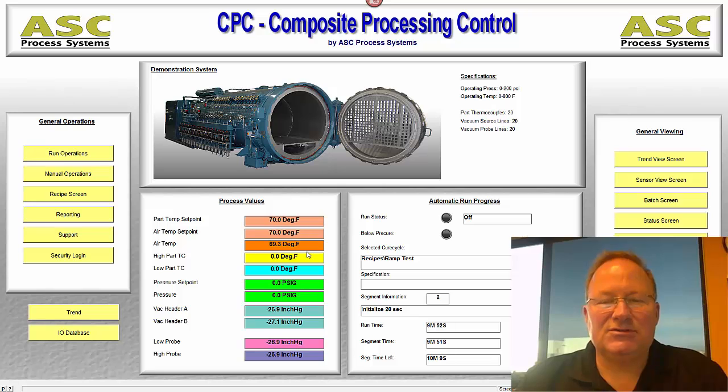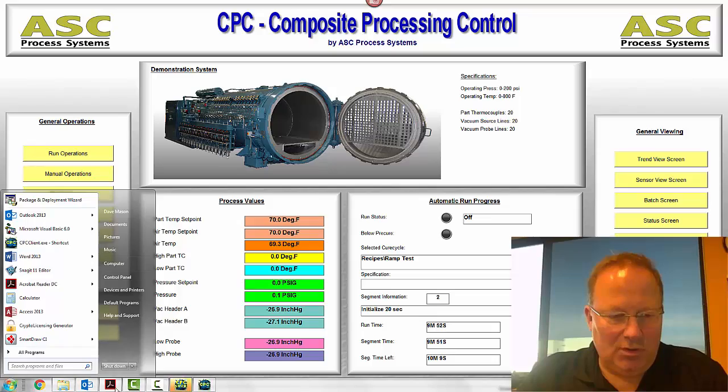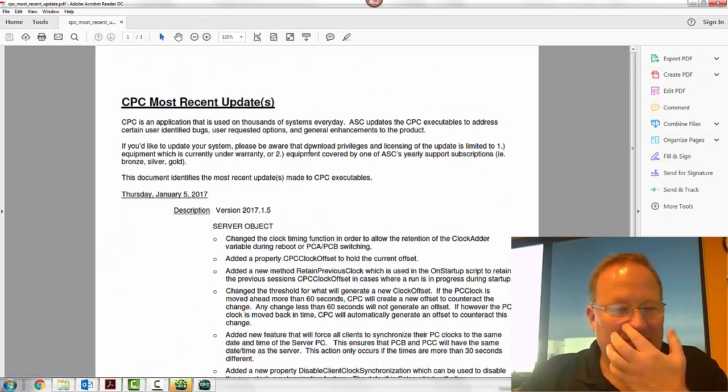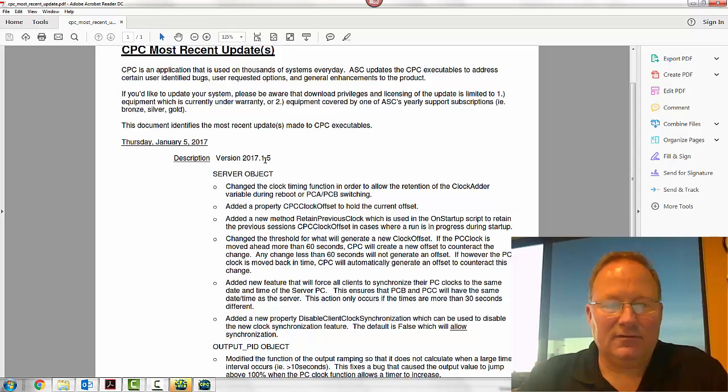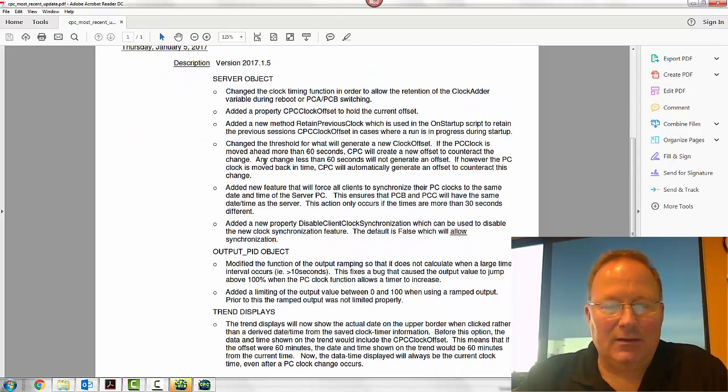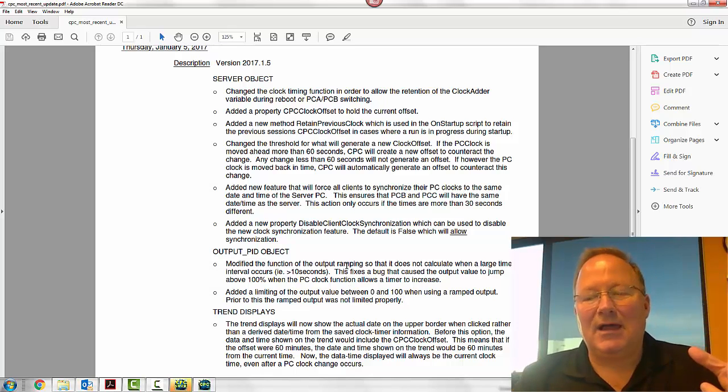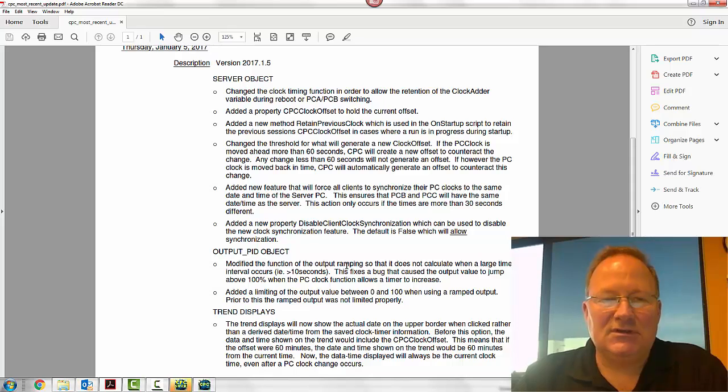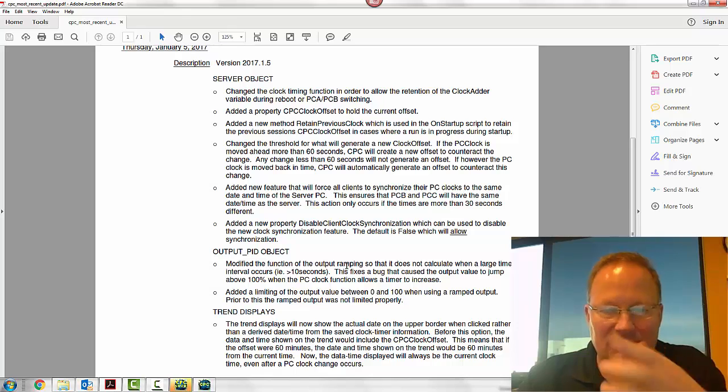This is a video where I'm going to talk a little bit about the inner workings of CPC as it regards to timers, and specifically the new update to CPC on January 5th of 2017. All of it has to do with timers and clock times, and a bug that was identified by one of our customers recently that caused a situation where pressure became uncontrollable for a moment, and the reason that happened and what we did to fix it.